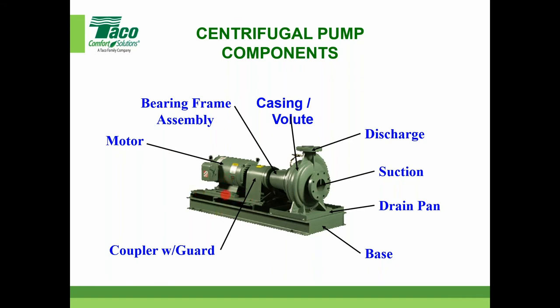And notice right here, there are some spacers underneath the feet of the pump. So in our thought process, when we design these bases, we actually allow for most of our pump combinations; there's six motors that would fit on the standard base. You just have some type of spacers as the motor shaft dimensions change, right? So the biggest one sits right on the base, and that's two frame sizes, 254 and 256. Then the next one's 145, 143, or 213, I think, or 215s. They may sit on one spacer, and then the 143s, 145s. These are all frame size motors. If you Google it or look it up, their centerlines are different, so we have even more spacers there. So it reduces the stock of bases that we have. So pretty much that's all I got.